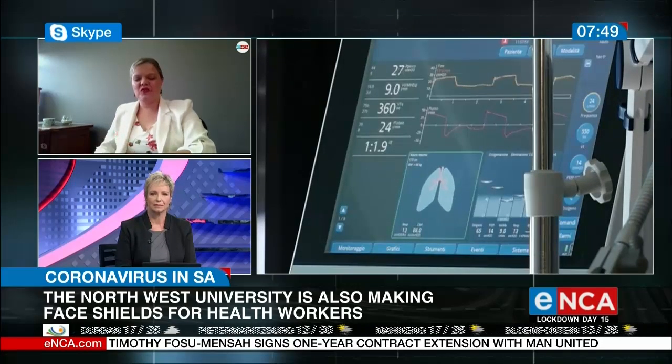Many people haven't been to an ICU, but if you have, you will know that the normal ventilators used these days are very complex, very intimidating devices that do a lot of complex electronic calculations and regulate breathing for the patient. A mechanical ventilator like the one we are investigating uses a very simple interface — normal knobs you can turn and valves to actuate the air. It is simpler to use, especially since the big constraining factor in the country is not only that there aren't enough ventilators, but there's also a significant shortage of trained ICU nurses able to use those complicated machines.